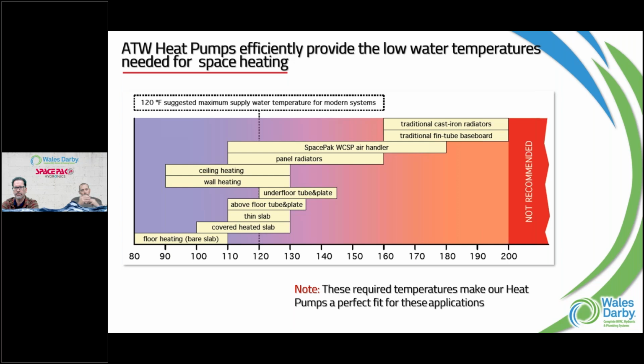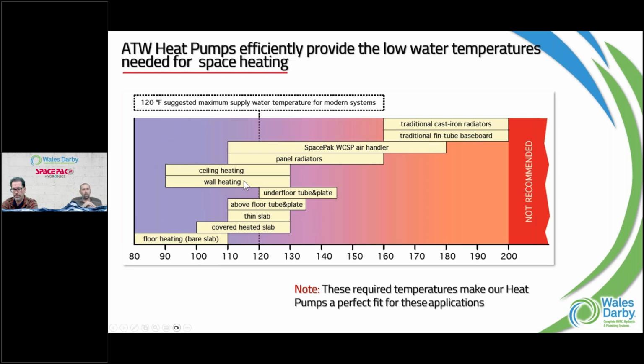But this always brings up good conversation of what we can do and where our sweet spot is. If we're talking that 120-degree range, that's the line right down the middle, or to the left, all these different applications between radiant, different types of radiant applications, panel radiators are in the conversation, high velocity, and those high wall thin wall units. It brings in a lot of these different conversations, and then traditional baseboard goes all the way up into that 160-and-above range. There are some baseboard manufacturers now that have low output ratings, so that line actually continues down further now to those lower 110s, 120s, 130s. So tons of options, and it's really up to you.